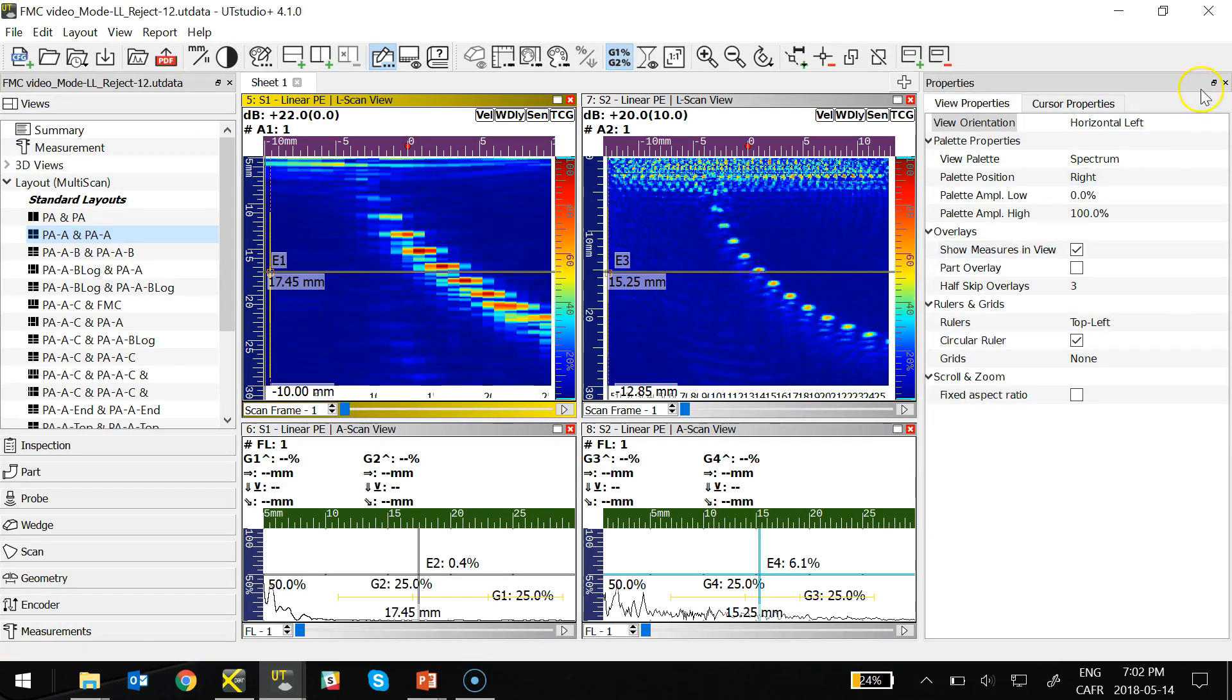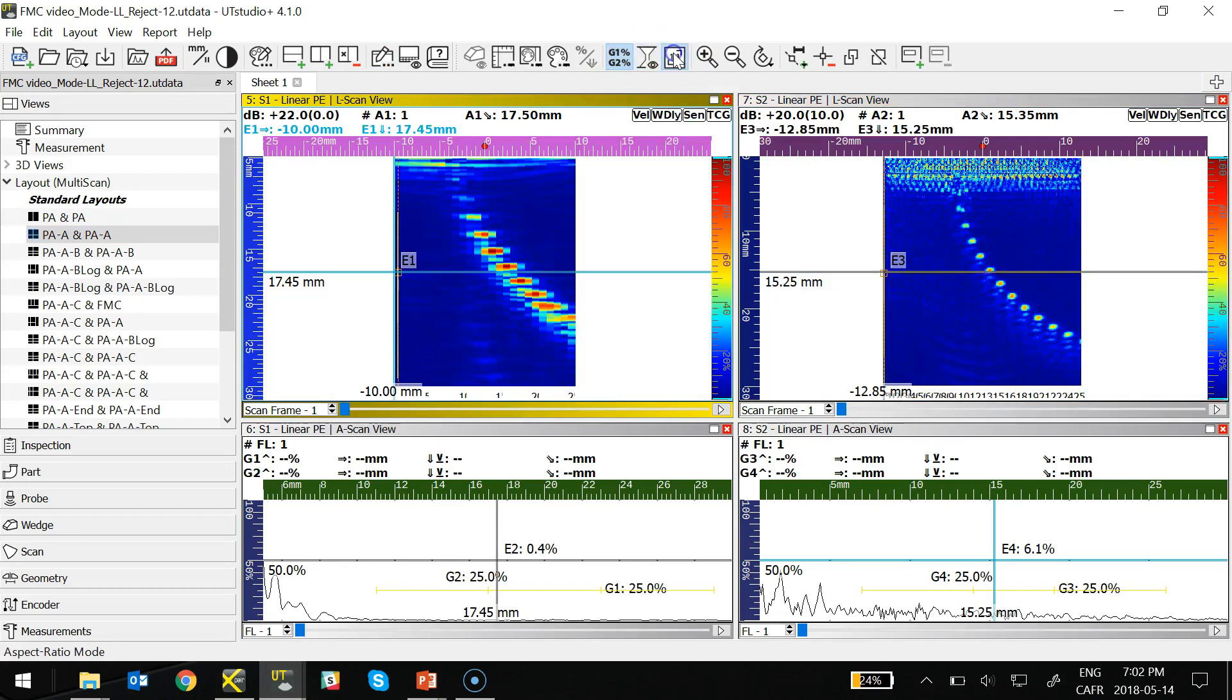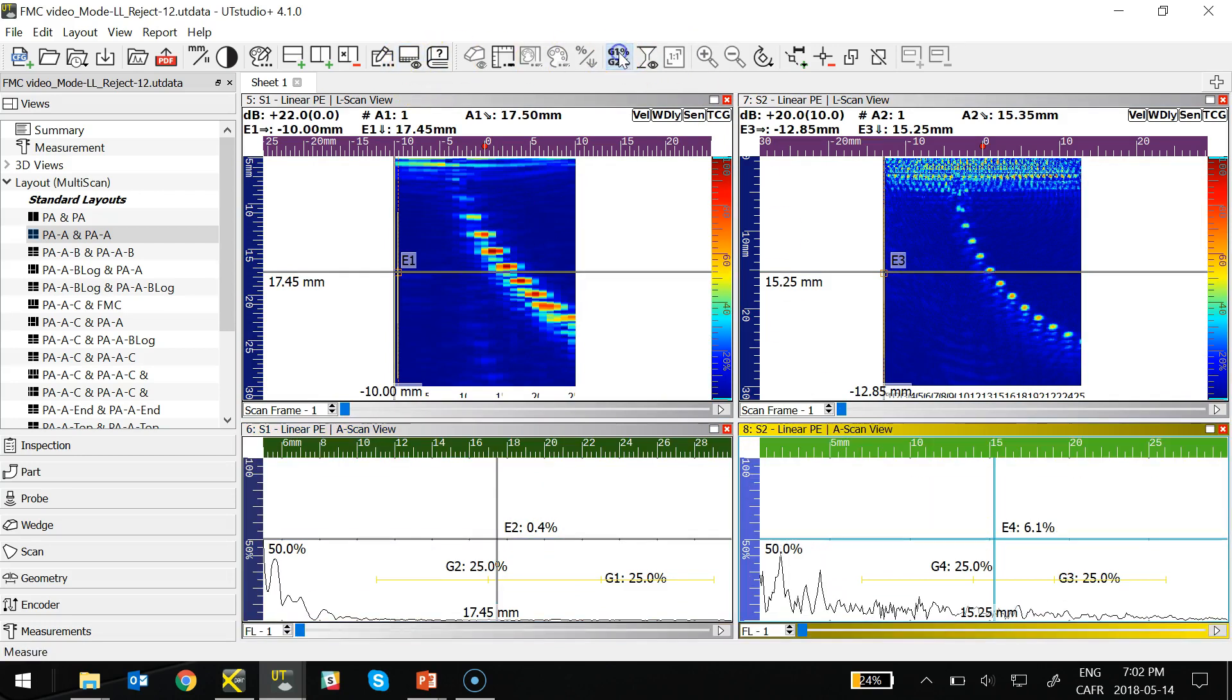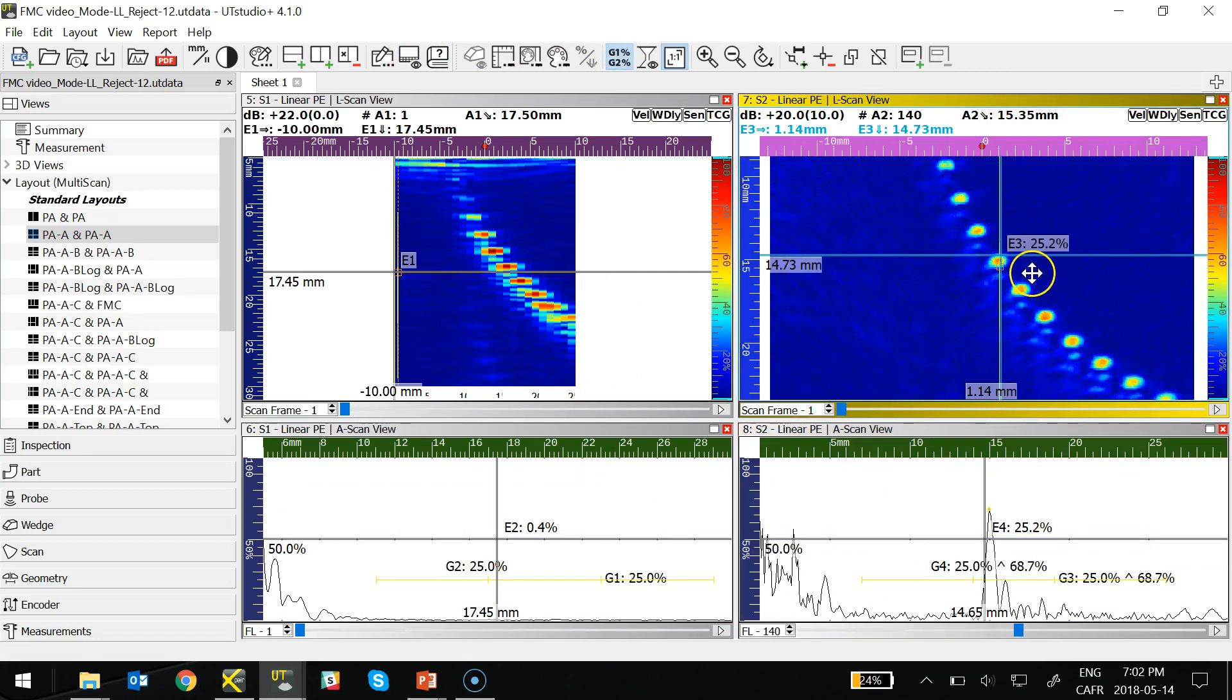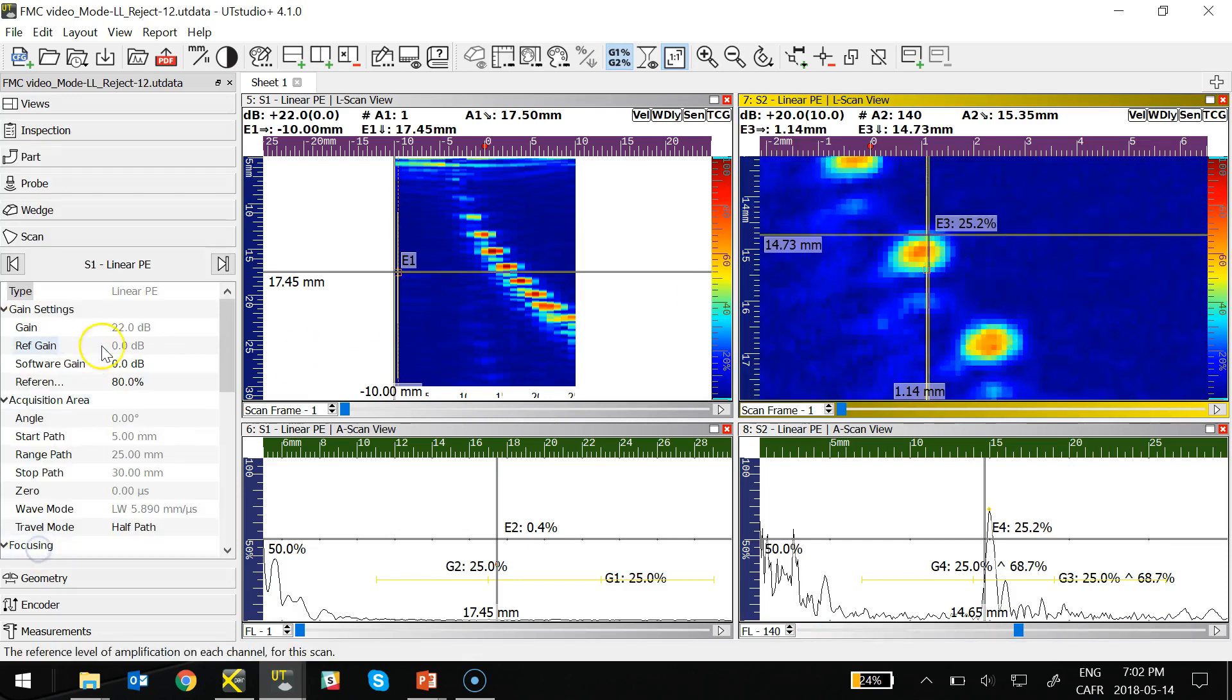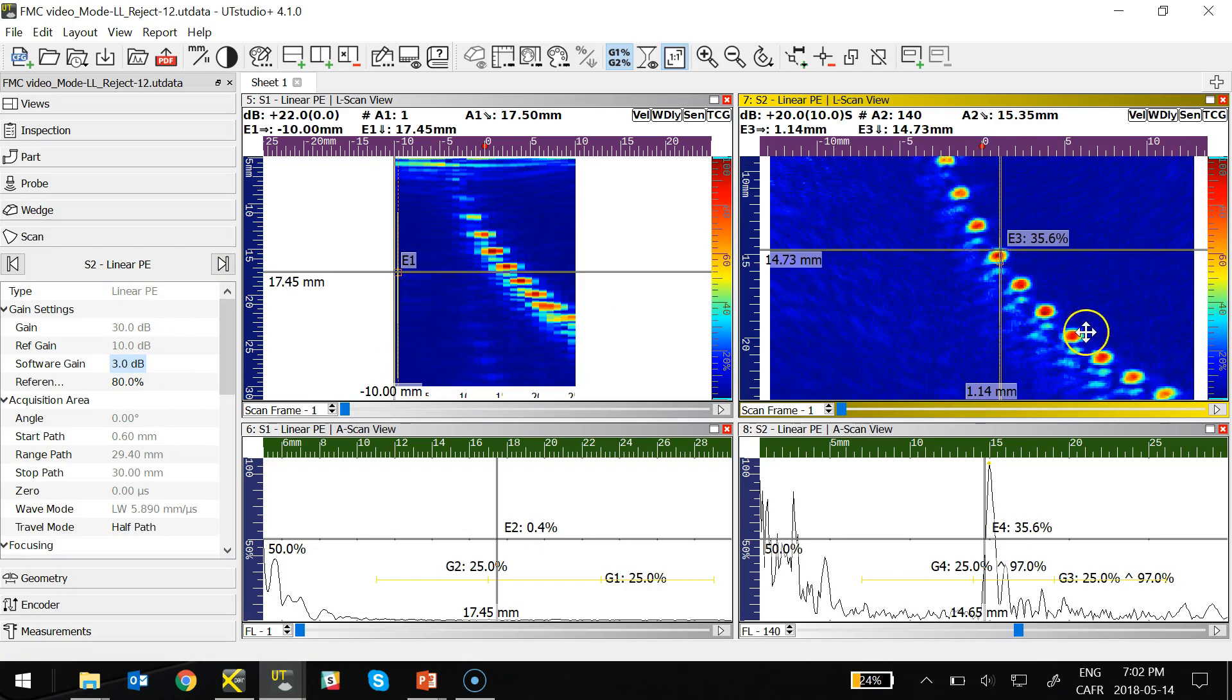Now, we can see here on the right that I have my TFM images, but also on the left that I still have access to my Phased Array scan. So on the left, I have my Phased Array scan, and on the right, I have my TFM scan. The interesting thing here is that I can compare both defects captured by Phased Array and TFM, and compare the analysis side by side.